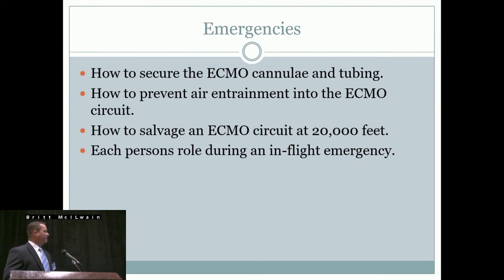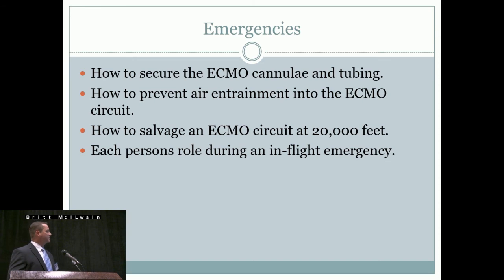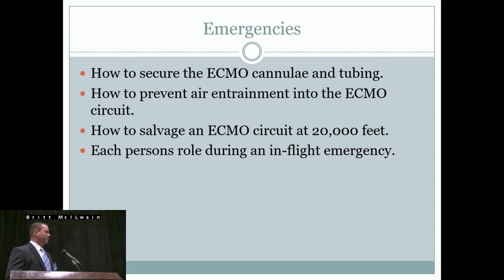For in-flight emergencies, you must know how to secure ECMO cannulas and tubing. The best approach is to prepare the circuit and cannulas so you don't have air entrainment. We use plunger caps or one-way valves on all stopcocks to reduce the risk of air entrainment. You need protocols for how to salvage a circuit at 20,000 feet, where everybody will be positioned, who will hand crank, who will work on the circuit, and each person's defined role.